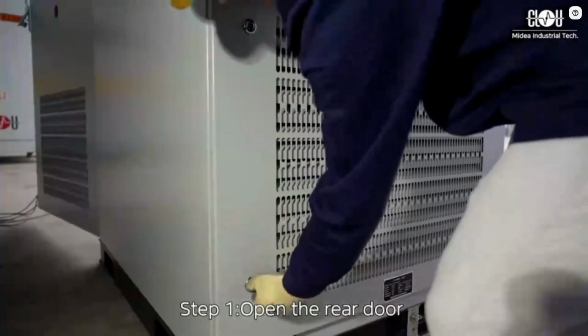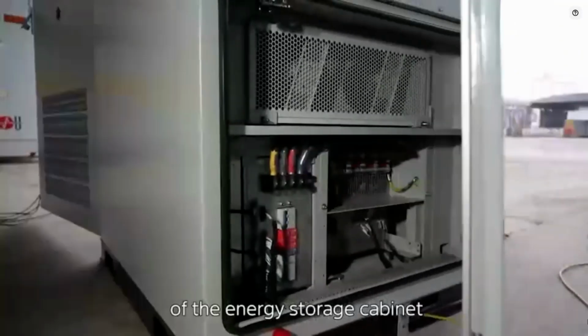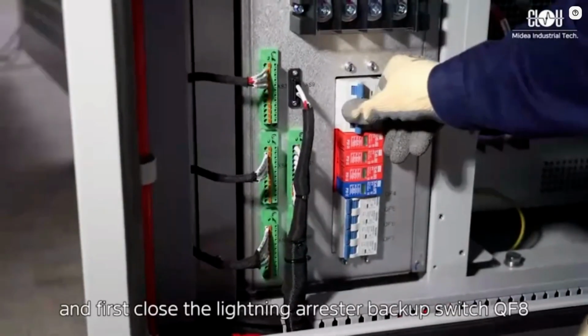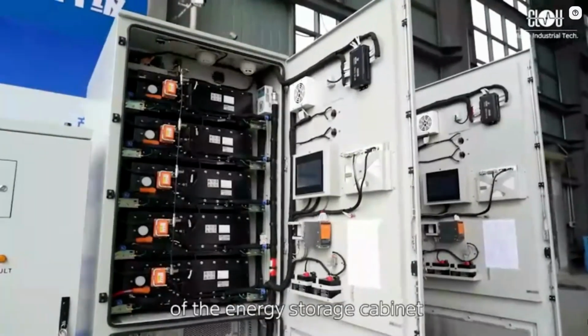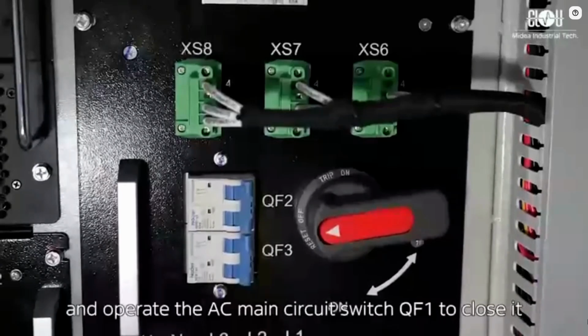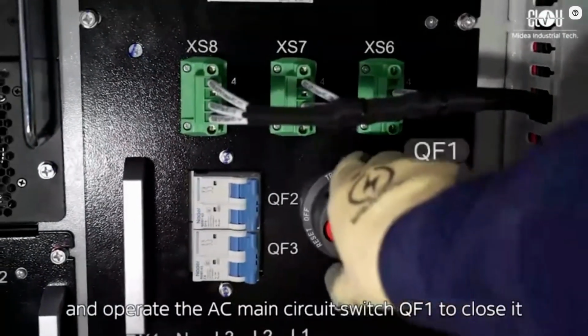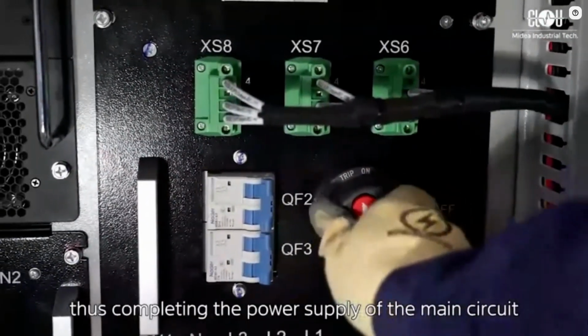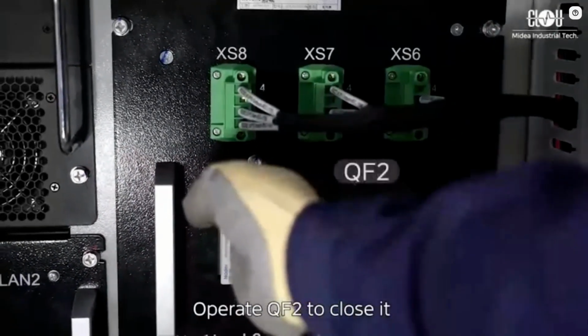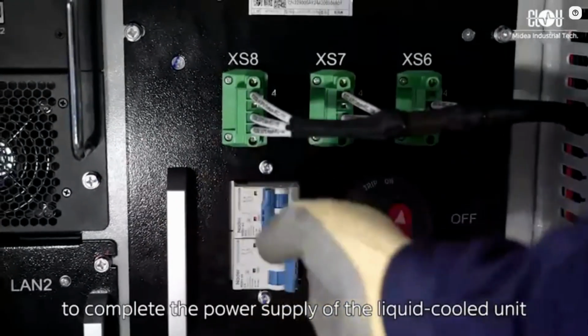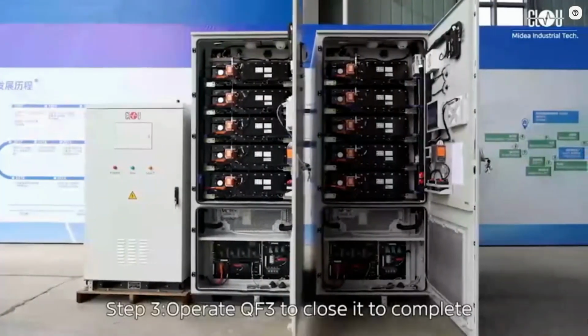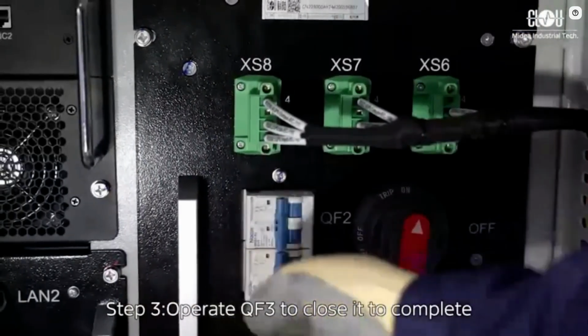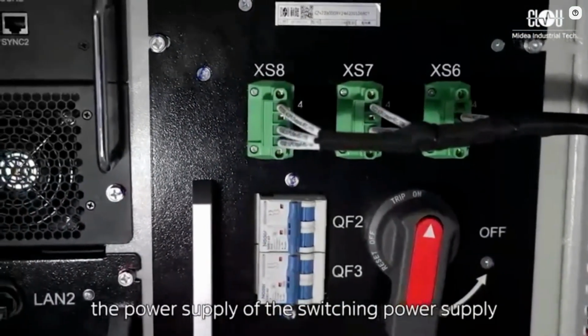Power transmission operation. Step 1. Open the rear door of the energy storage cabinet and first close the lightning arrestor backup switch QF8. Then return to the front door of the energy storage cabinet and operate the AC main circuit switch QF1 to close it, thus completing the power supply of the main circuit. Step 2. Operate QF2 to close it to complete the power supply of the liquid-cooled unit. Step 3. Operate QF3 to close it to complete the power supply of the switching power supply.